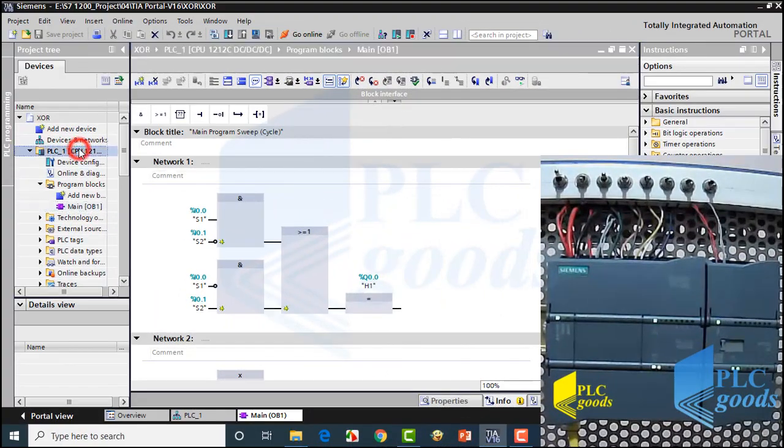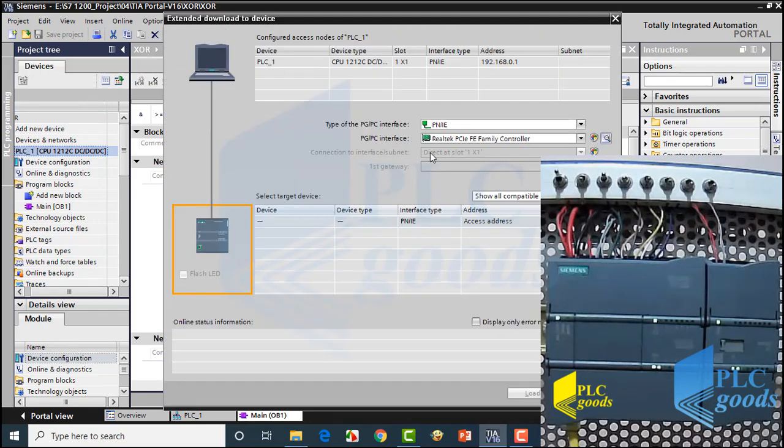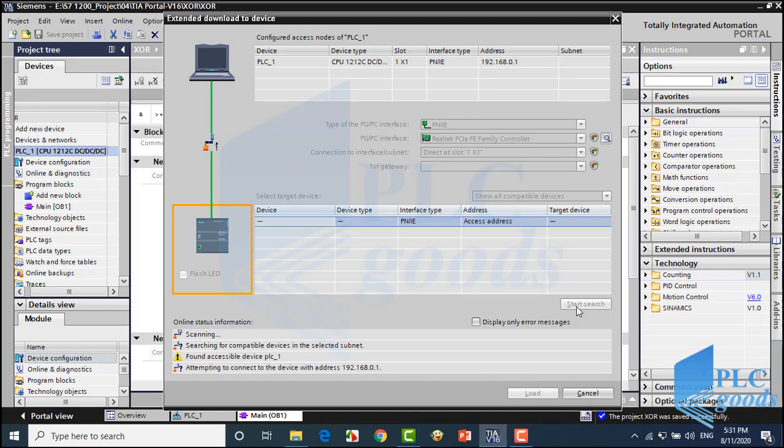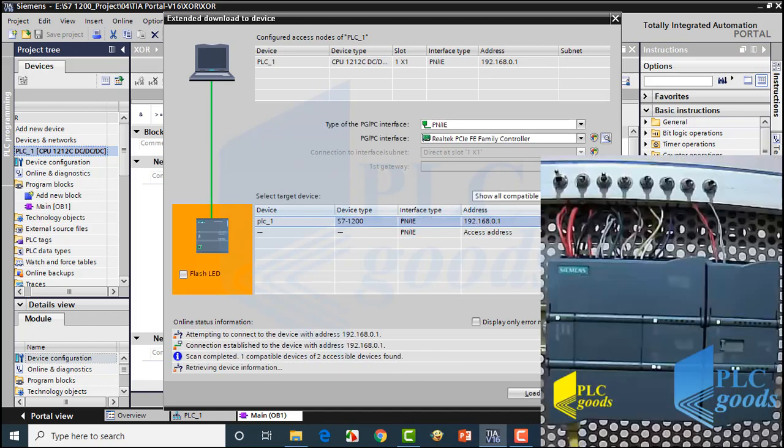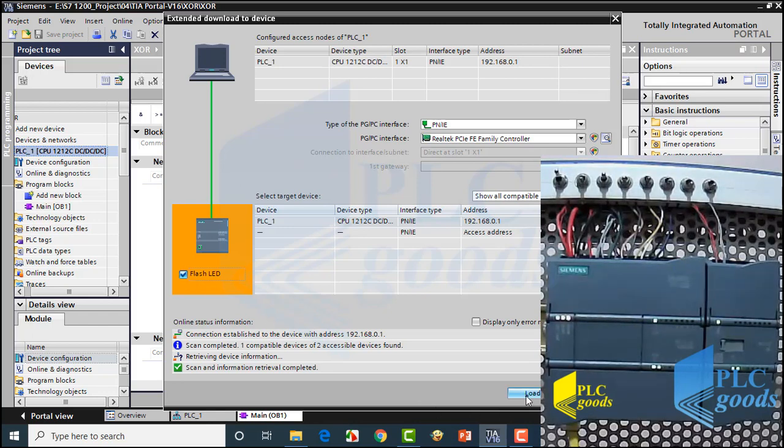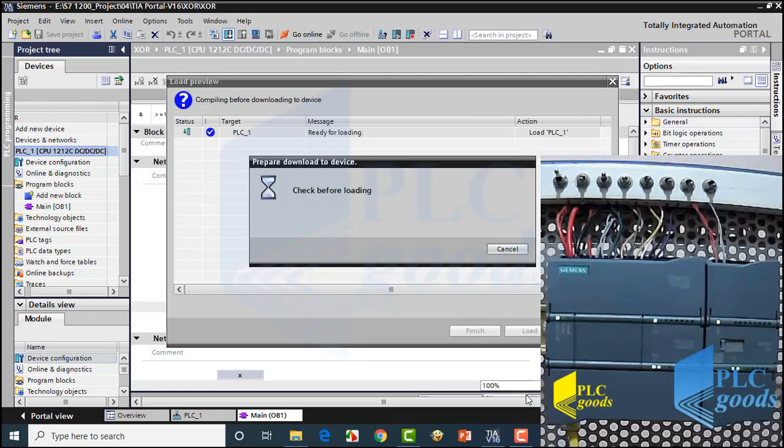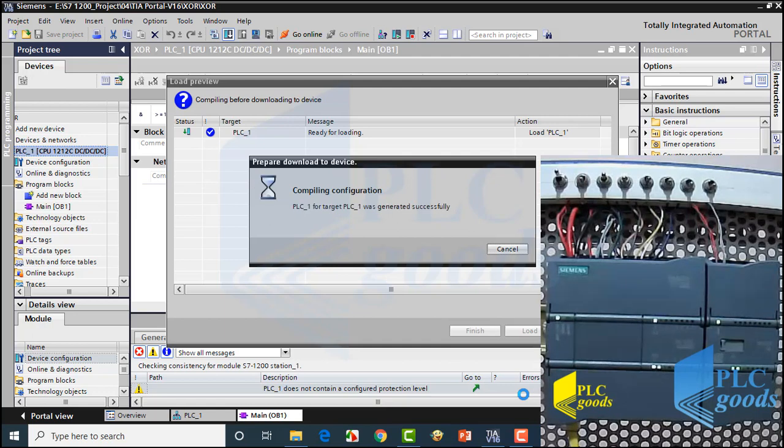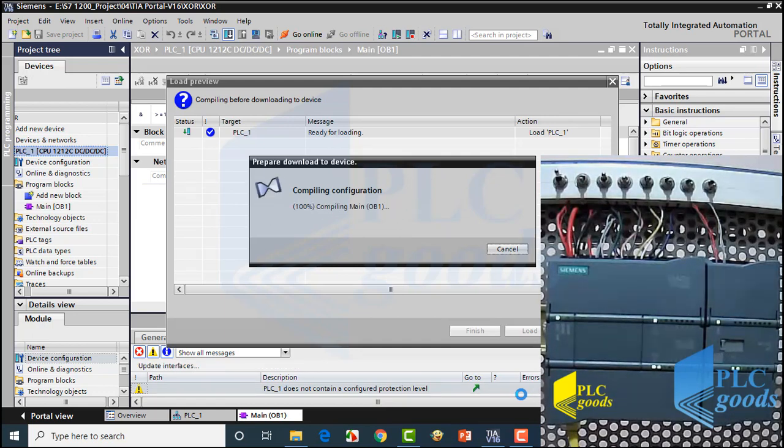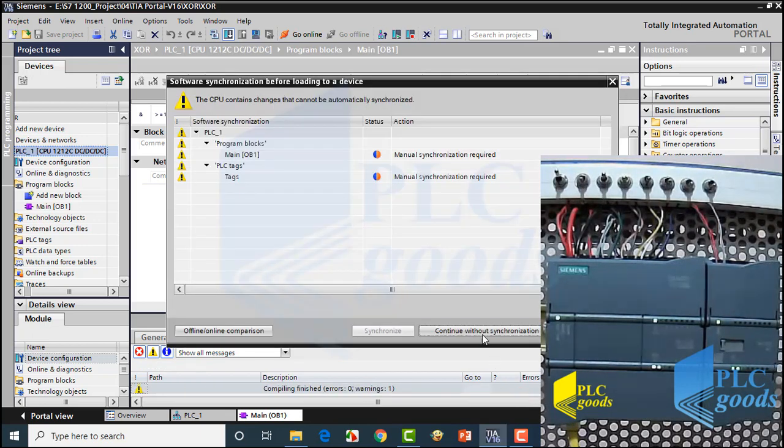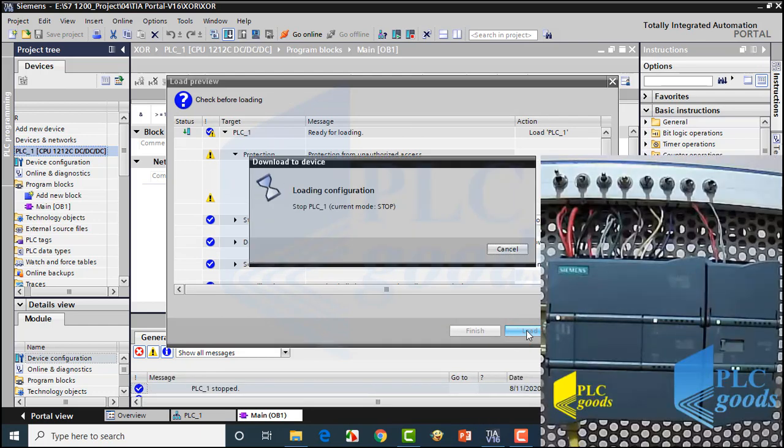Similarly, I can transfer the XOR program to my PLC. Here I click on search to find my PLC. The main point is, I've closed the virtual PLC, otherwise TIA won't find the connected PLC. As you know, if I click here, the selected PLC starts flashing. Let's load the program to the selected PLC. Well, before loading, PLC needs to stop all modules.